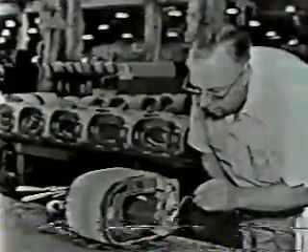That man there is now brazing one of the connections between the inner low voltage coil and the outer low voltage coil. That forms the interconnections, and on the other side, of course, the leads will then go out to the bushings for the actual service operation. Now, so far we have the coil manufactured. What will happen to it next?